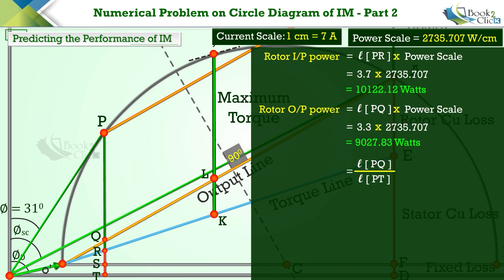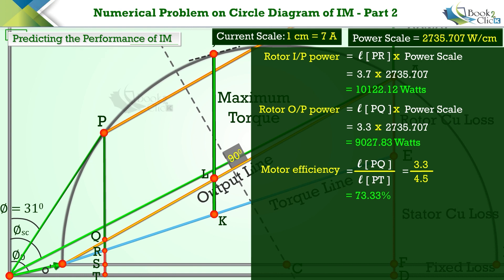Divide the length of line PQ by PT to determine the motor efficiency. The length of PQ is 3.3 centimeters and PT is 4.5 centimeters, so the motor efficiency is 73.33%. Divide the length of PQ by PR to determine the rotor efficiency. With PQ at 3.3 centimeters and PR at 3.7 centimeters, the rotor efficiency is 89.19%.